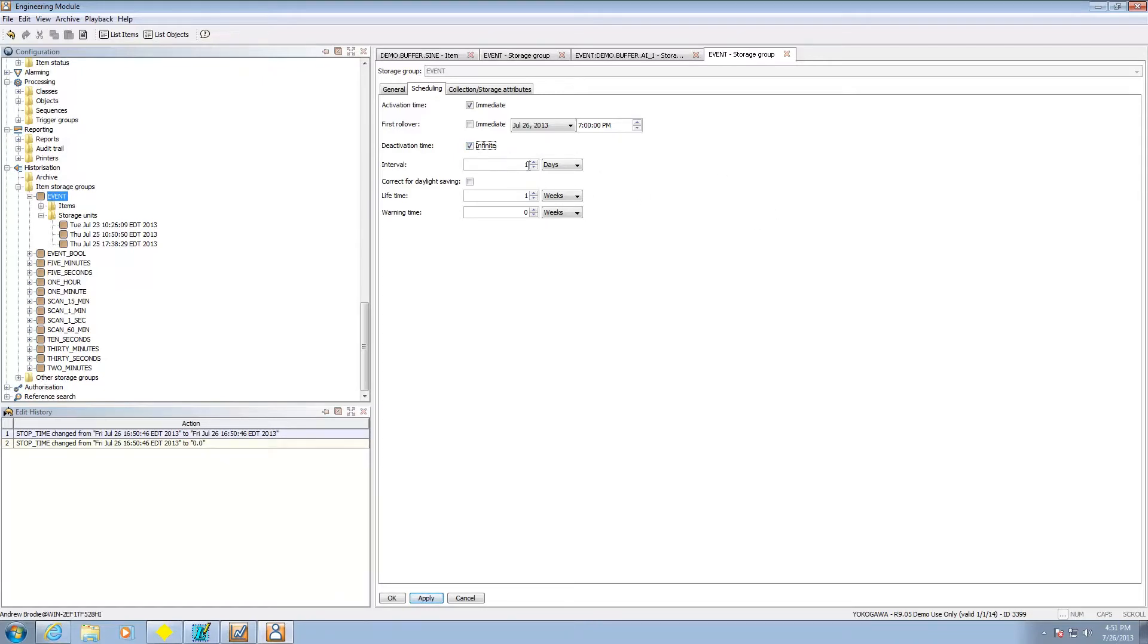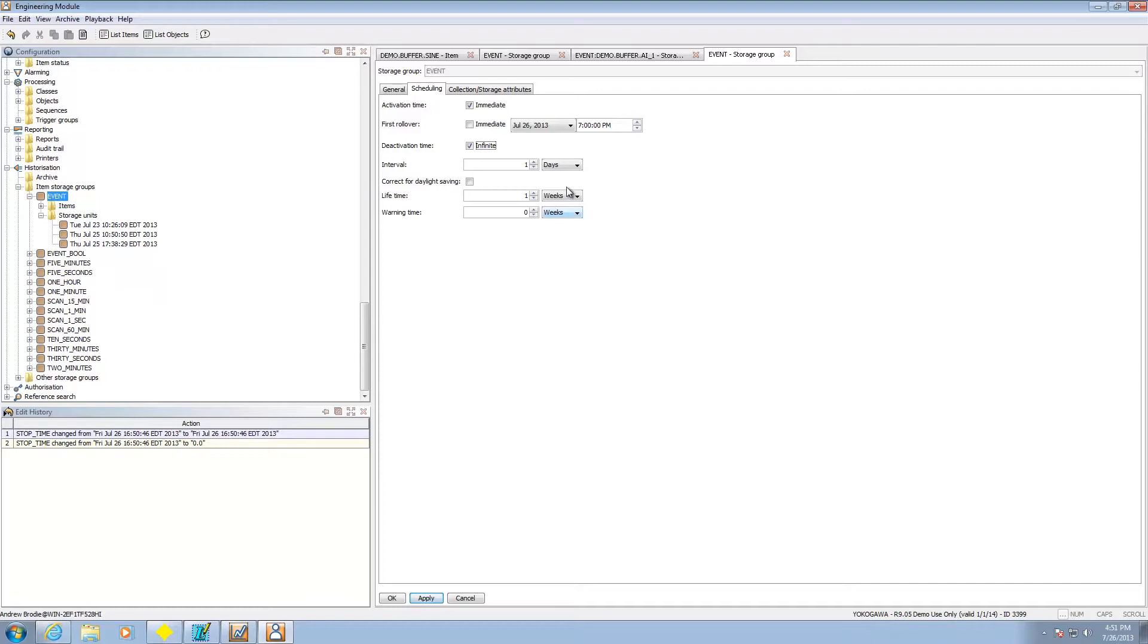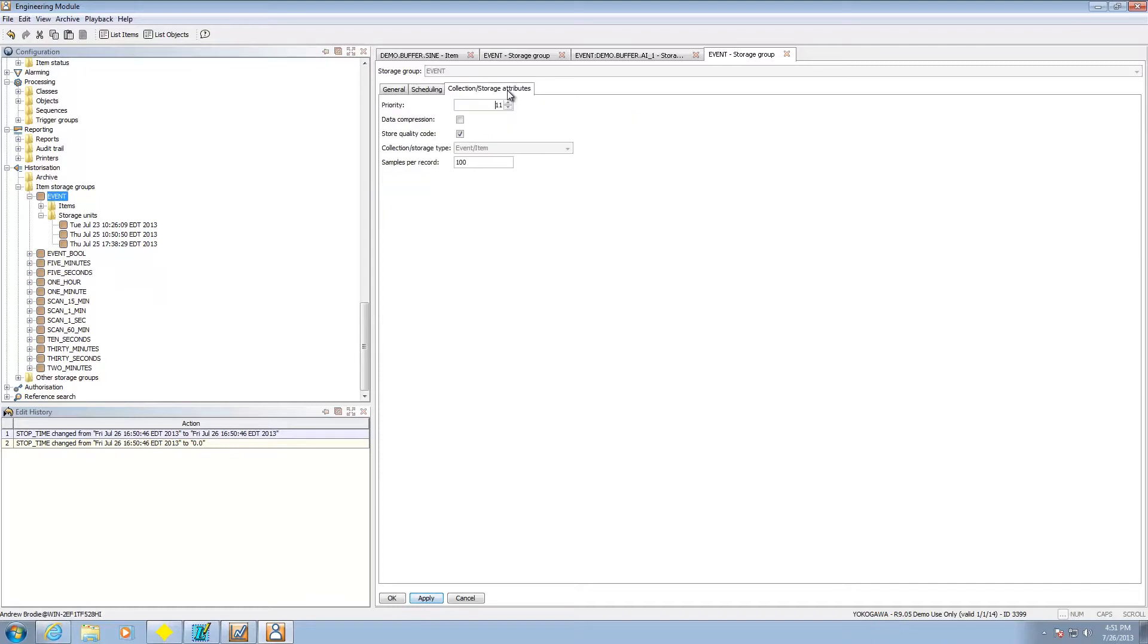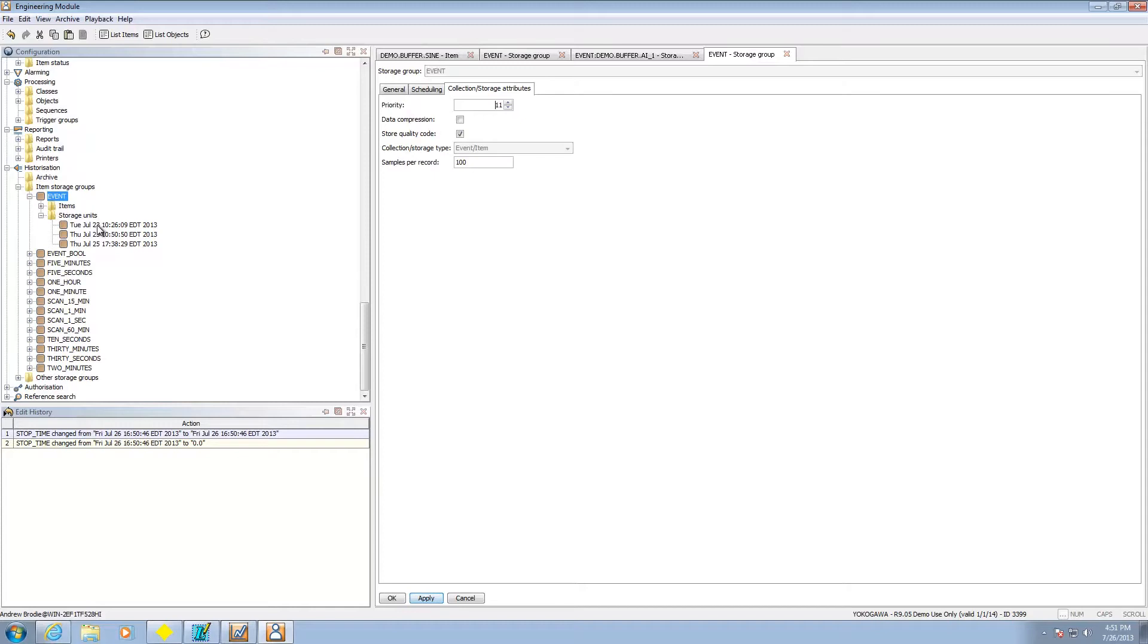How often I'm going to create a file every day. How long I'm going to keep those files. In this case I'm going to keep it for a week and then I can do a warning time as well so I can let you know before I get rid of stuff. Collection storage attributes. I can do stuff like data compression, store quality code if it's available. Those are probably the major things you need to look there. Storage units. This is just how many of those data files it's gone ahead and collected.